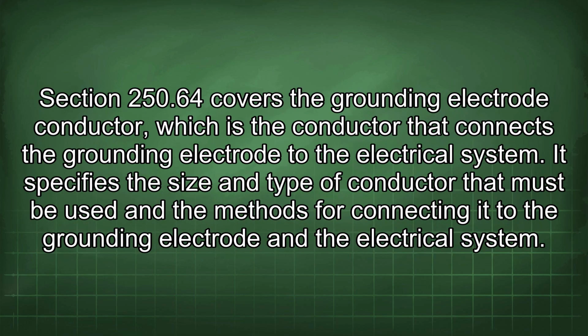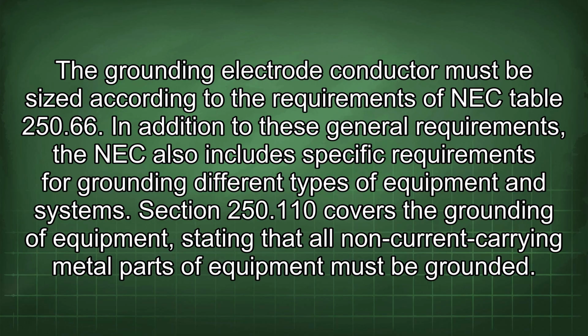Section 250.64 covers the grounding electrode conductor, which is the conductor that connects the grounding electrode to the electrical system. It specifies the size and type of conductor that must be used and the methods for connecting it to the grounding electrode and the electrical system. The grounding electrode conductor must be sized according to the requirements of NEC Table 250.66. In addition to these general requirements, the NEC also includes specific requirements for grounding different types of equipment and systems.